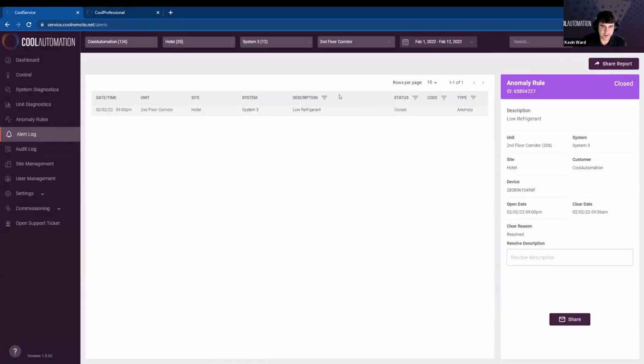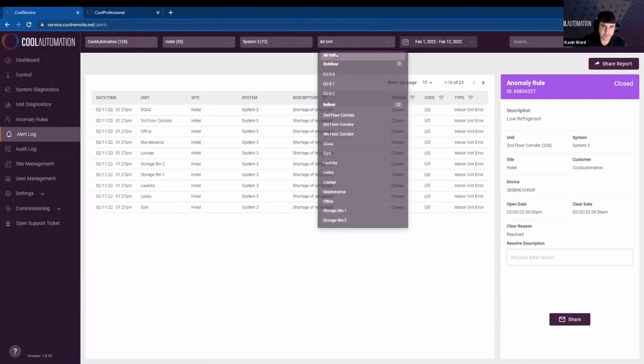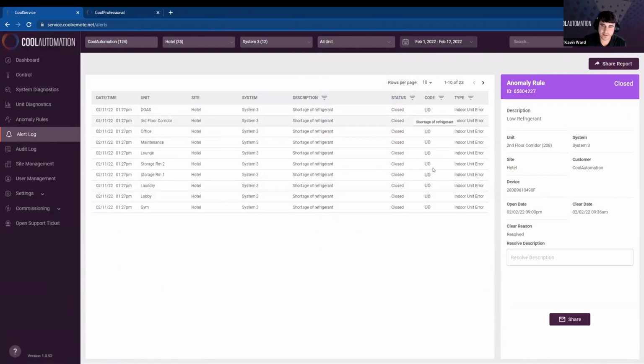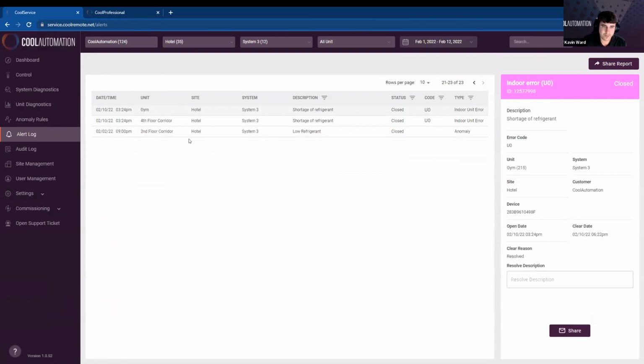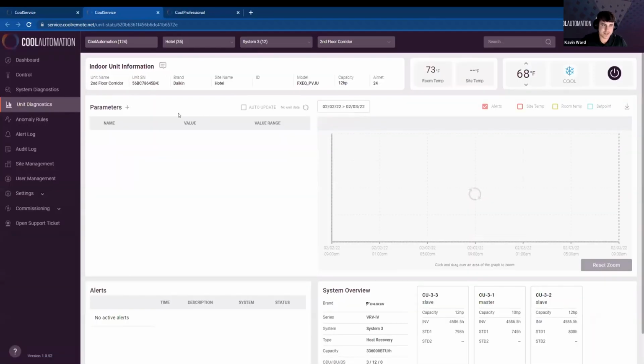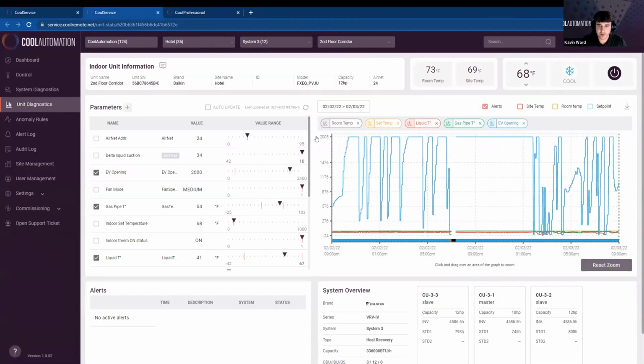So in our alert log for the system, we can see that the U0 error code where the system actually faulted out occurred on February 11th. If we go back, we can see that there was an anomaly rule that triggered over a week prior to the system faulting out. So simply double clicking this anomaly rule will bring you back to the unit diagnostics section with your parameters preloaded with that anomaly overlaid onto the graph here.